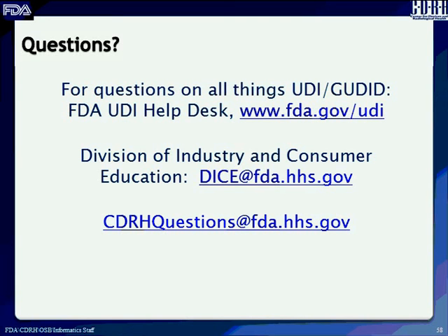No. I'm looking at page 5 right here. This refers to the requirement in the UDI reg in 21 CFR 801.3. The UDI is required to appear on the label of the finished medical device and every device package for that finished medical device. But direct marking of devices is something entirely different and something that Indira covered for database purposes very briefly, but that's not what this refers to.